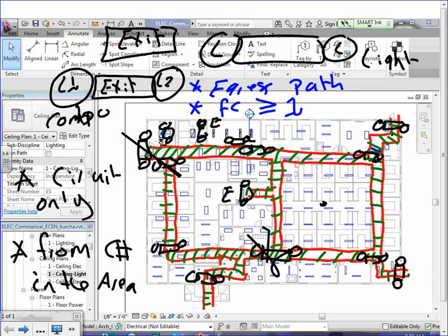If you guys are proficient, as you will be, Darren, with the emergency light, the exit signs, the parking lot, and the energy code, when you know the software, for a system like this you're looking at a day of work, stretching it for one person. That's even stretching it in the real world. But you don't have Chad to interrupt you every day and yak at you. So 8 hours, you should be able to put all your emergency lights, circuit them, parking lot lights, circuit them, do the energy code, and that's stretching it too. But again, you don't know the software. There's a lot of bugs here and there.